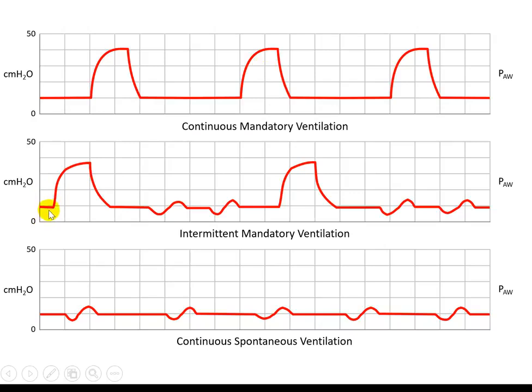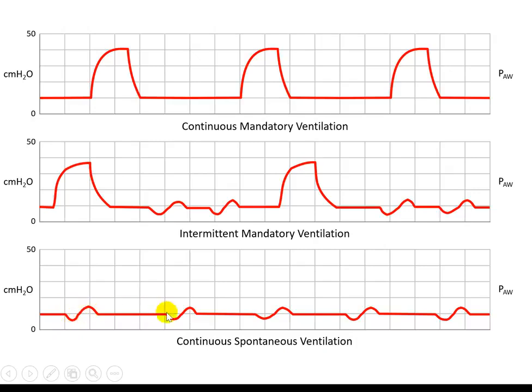In intermittent mandatory ventilation, the patient has some spontaneous breaths in between mandatory breaths. Those spontaneous breaths can also be supported with pressure support, giving pressure supported breaths in between. The mandatory breaths can be synchronized with the patient's efforts and delivered at the same time the patient is breathing, forming assisted or synchronized breaths — and this is how SIMV mode is formed. If all breaths are spontaneous, this is continuous spontaneous ventilation, and supporting those breaths with pressure support transforms the mode into pressure support ventilation.